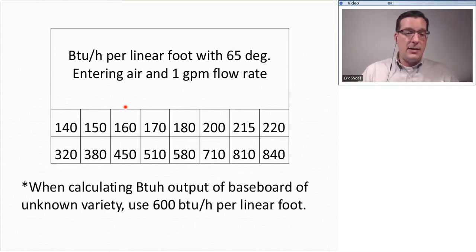And what this shows us is that at 140 degree water temperature, its output is 320 BTU per foot. So if we have 10 feet, that's 3,200 BTU for that 10 foot section of baseboard. As water temperature gets higher, so does the BTU per foot output. And we're generally looking at a water temperature of around 180 to 200, and that is pretty much the sweet spot we look for. Copper fin baseboard is designed to operate with water supply temperatures around 180. Same thing with the cast iron baseboards and the cast iron radiators. We're looking for 180 to 200 degree water. We generally round that to 180.